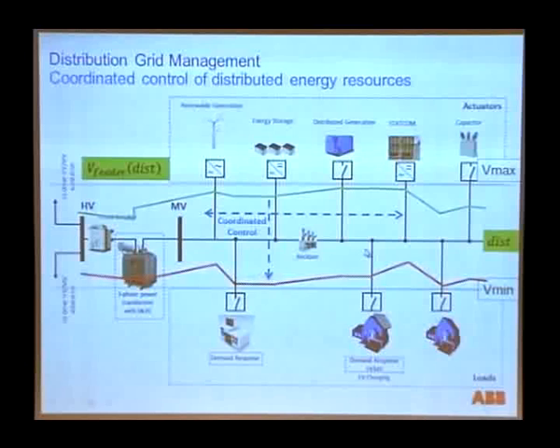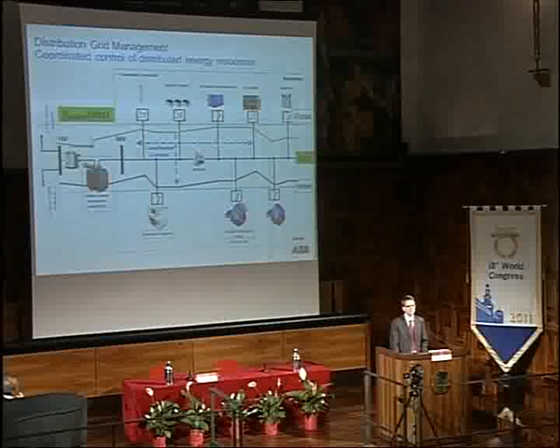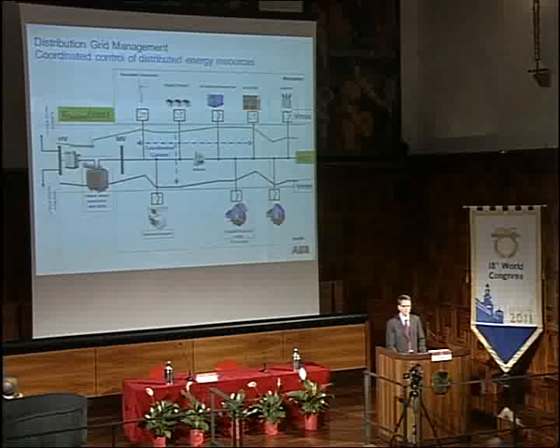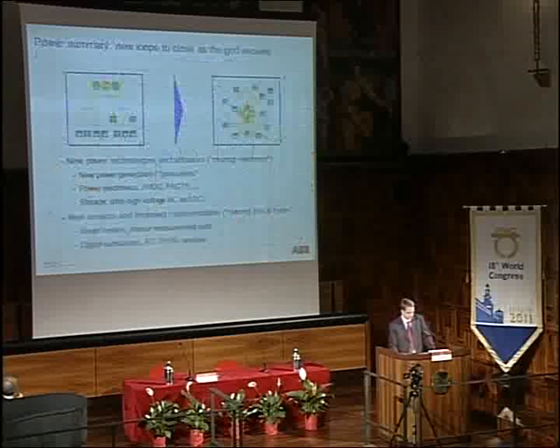One of the big factors here is managing your reactive power properly, which doesn't help your consumers but loads the grid, and today on the distribution grid level that's rather empirically managed. A capacitor bank is maybe switched in at 7 in the morning and switched out at 8 in the evening, rather than switched based on actual current and voltage measurements. So it's a great opportunity. In the first project where we deployed this with a US distribution utility, we've achieved in the order of 2% savings with this strategy, which is quite an amount given the power a utility is providing.